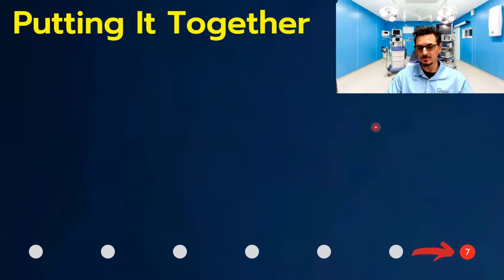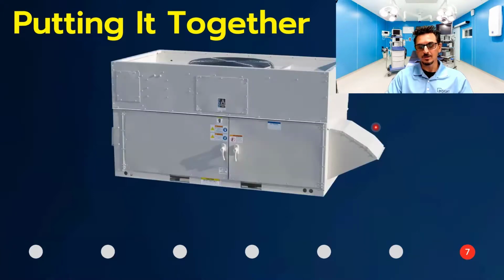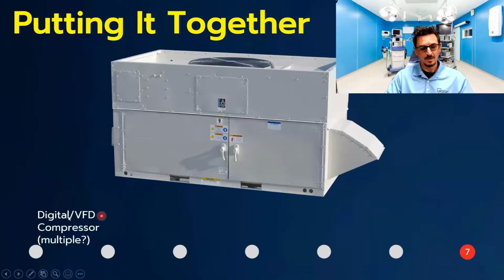All right, so section 7, we are almost done, and we're going to have a few minutes for questions, which is great. And again, we really do appreciate everybody joining us. So let's put all this stuff together real quick in the unit, in the specialized DX piece of equipment we're building with all the features to meet our design objective in the surgery suite or other low dew point applications. So digital or VFD compressor. I put multiple question mark because if you have the ability to do multiple compressors, it's probably better. Of course, we look at that on a design basis and make that determination.